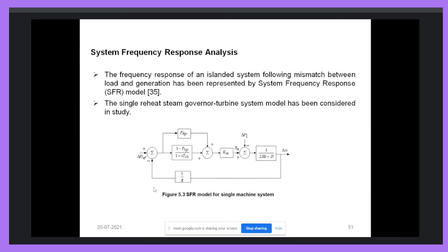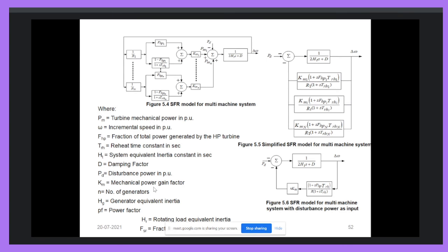Now the frequency stability analysis is performed to determine the system frequency. Okay, this is the SFR model of the single machine. Here del P is the mismatch in power, and del omega is the change in frequency. So we have to analyze the system frequency response for every possible mismatch between load and generation. Okay, so we will have the frequency deviation for each and every amount of mismatch in load and generation. Then only will we be able to design under frequency protection or load shedding protection. This is the system frequency response analysis.